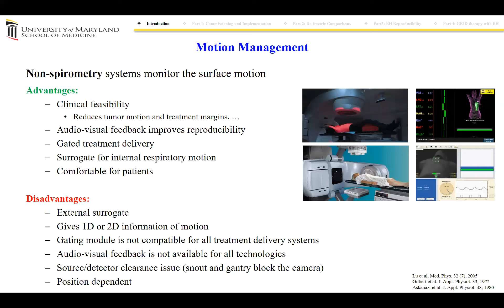There are some problems, mainly for protons. One is the source-detector clearance issue. For example, in the Vision RT system, usually we have the snout and gantry blocking the camera, so we can't get good information of the surface. Also, in some of them it's position dependent. If you're using the RPM system, the position of the block can change what you get in the motion management. The non-spirometry system has other advantages, similar to the others: it reduces the tumor motion and treatment margin, you can have audio-visual feedback, you can have gated treatment delivery, it's a surrogate for internal respiratory motion, and it's easily portable.